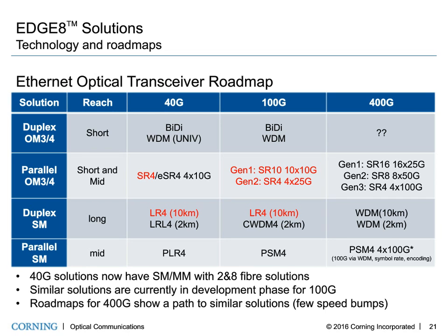If you went down to single mode, you had the same thing. You had parallel single mode, which was relatively cost effective in the data center space. And then you had 2 fiber single mode. Historically, 2 fiber single mode was a 10-kilometer solution. It was not cost effective in the data center space. But people saw what was playing out in multimode and said, hey, we need something to potentially run longer than multimode, but it doesn't have to run 2 kilometers, right?